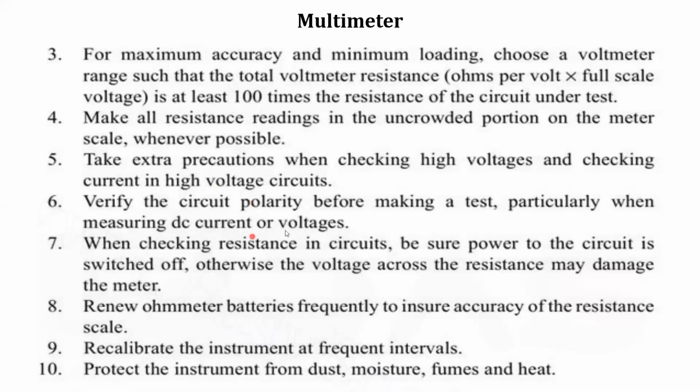Verify the circuit polarity before making a test, particularly when measuring DC voltages or currents. When checking resistance in circuits, be sure power to the circuit is switched off. Otherwise, the voltage across the resistance may damage the meter here. When checking resistance, the power to the circuit should be switched off, and then the measurement should be made.